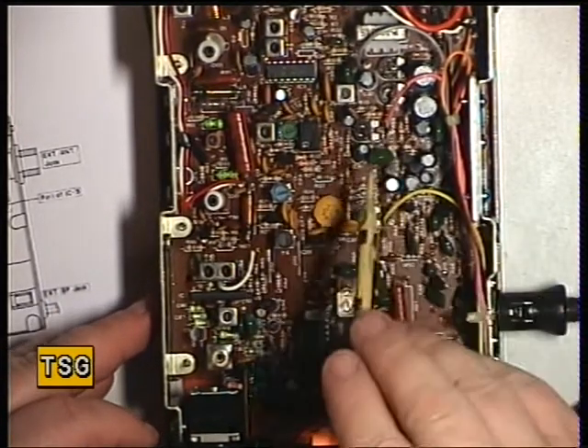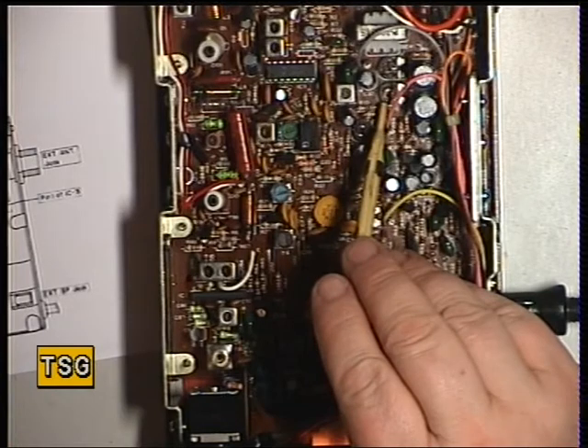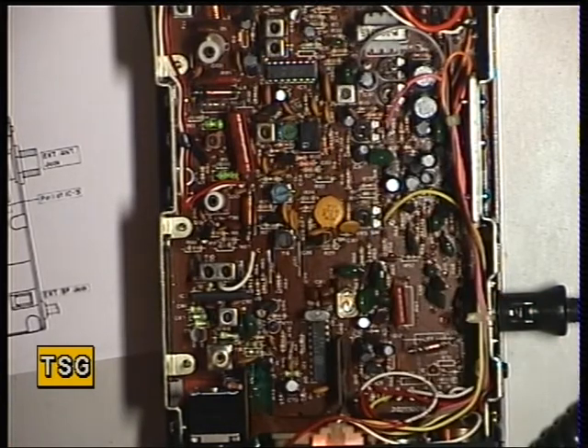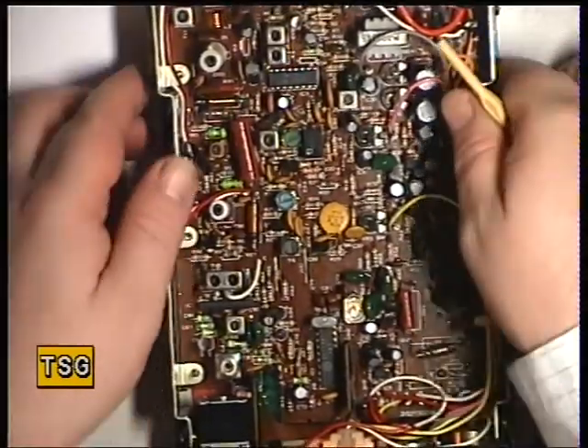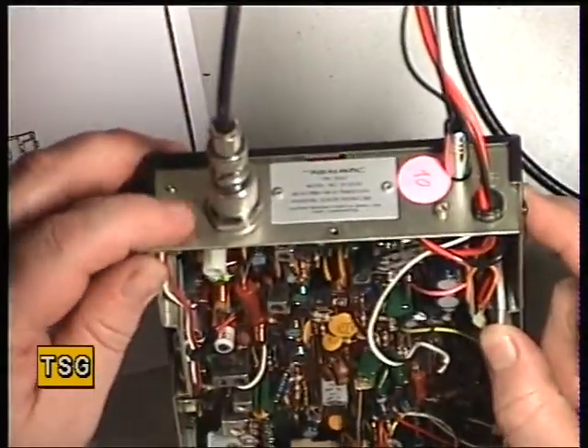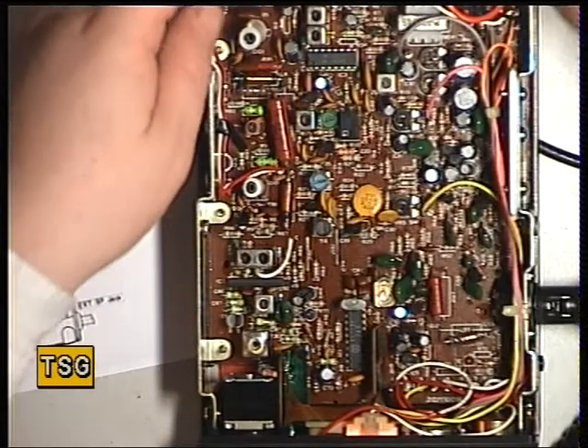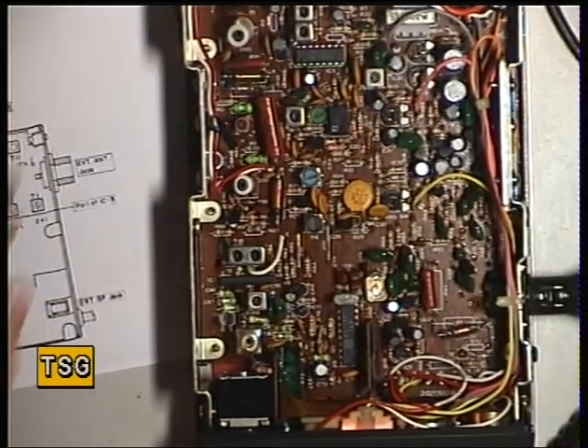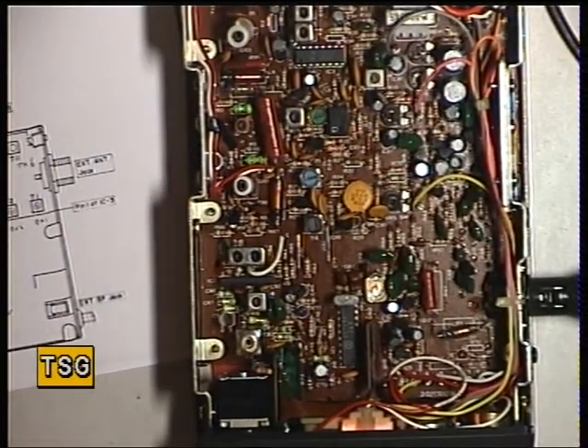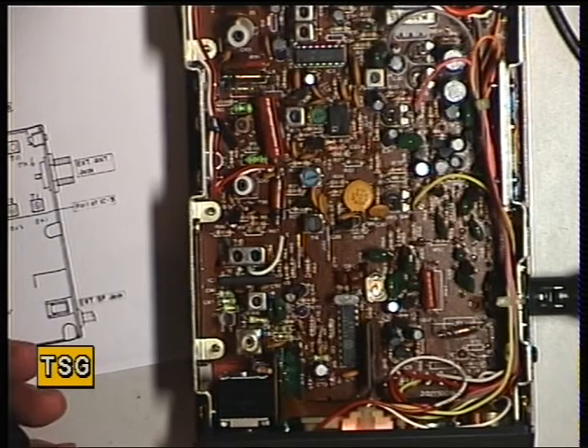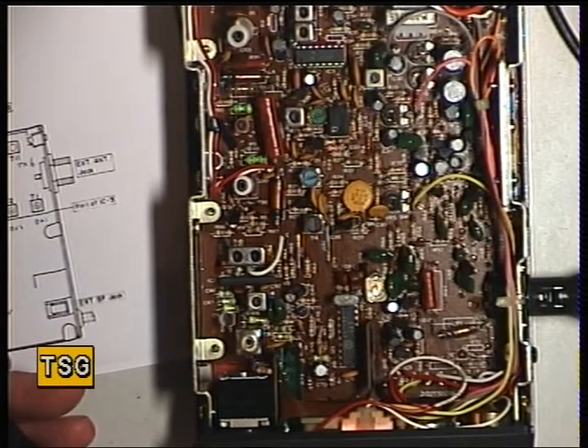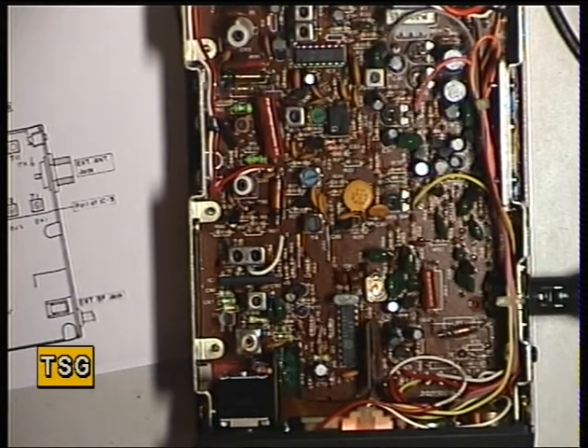If it needed adjusting, as I say, it would be VR4. Now, low power, when I switch to low power, there's a little switch at the back on these, it should be 0.4 of a watt. It isn't adjustable, but if it's out of tolerance by a long way, the service manual tells you how to calculate a different fixed resistor. So I'm now going to check that. Should be 0.4, it's 0.38. That's fine.